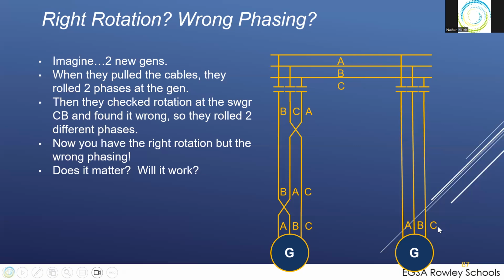Sometimes your VAR power factor regulators can give you a problem if we're only looking at a single phase, because now you're looking at the relationship between A and C over here and B and C. So while this will work, and it's done quite a bit with different machines, when it comes to balancing and reading, it can cause you problems. So be careful of that.